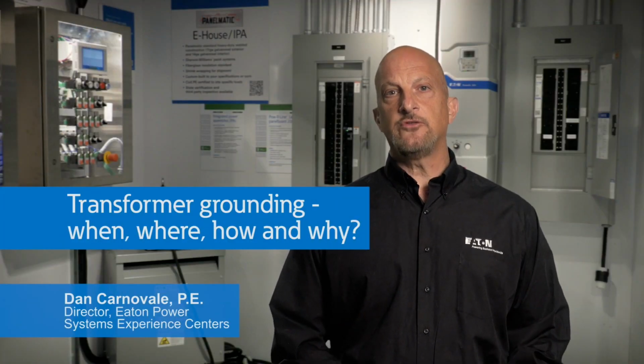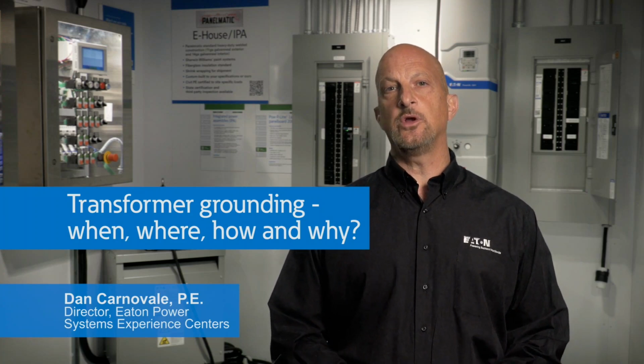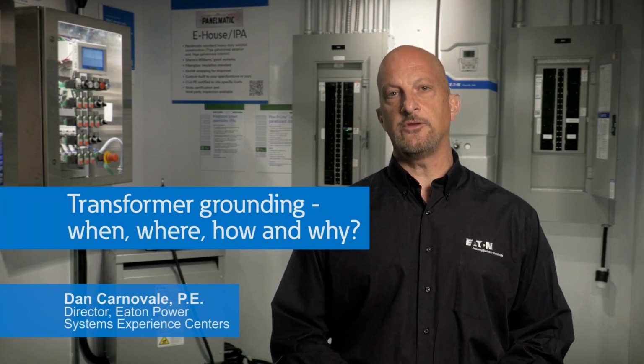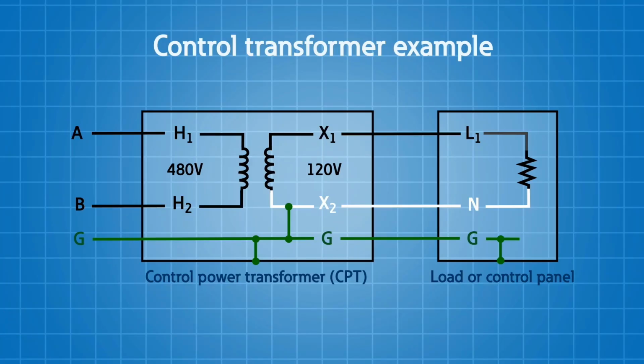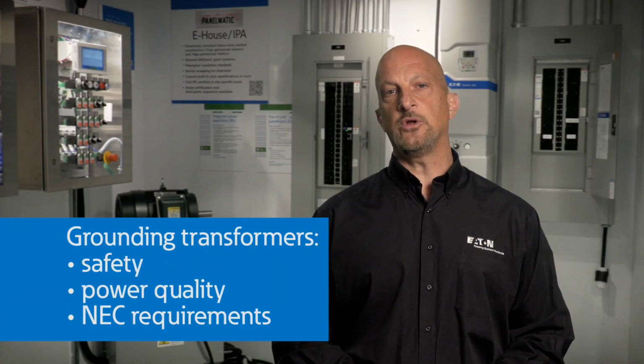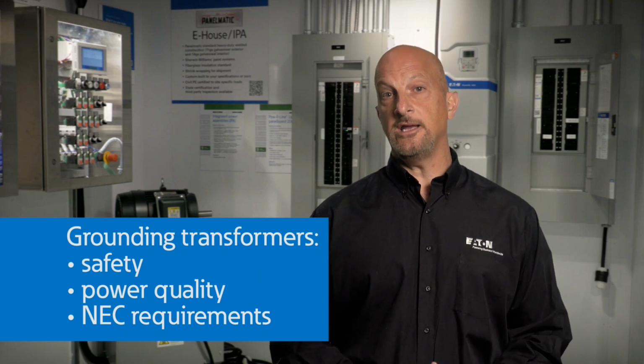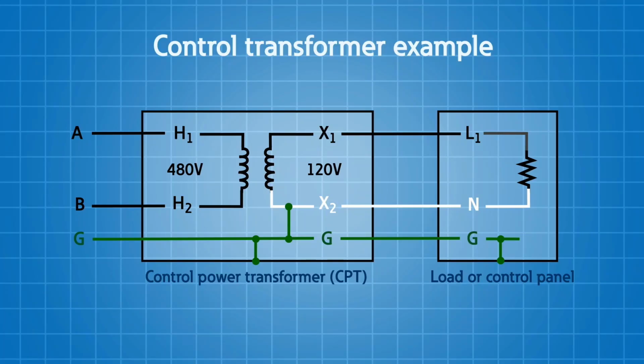With respect to grounding, transformers are often an area of concern and discussion regarding when, where, how, and why to ground the transformer. This is a simple single-phase example of a transformer like a 480 to 120 volt control power transformer. Considering the secondary windings, one of the two legs, typically X2, would be connected to ground. This would allow you to establish a known reference on the secondary of the transformer when this is required for safety, power quality, or by NEC requirements. X2 is also considered the neutral conductor for typical low voltage applications and would only be grounded at the transformer and at no other point downstream on the circuit fed from the transformer.